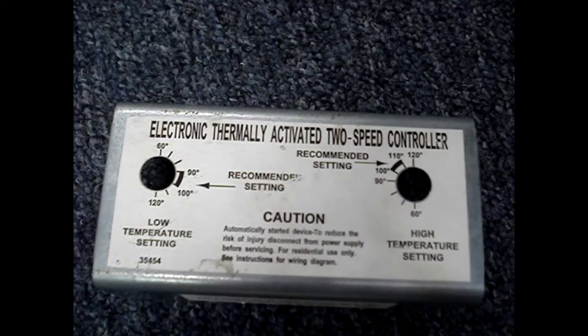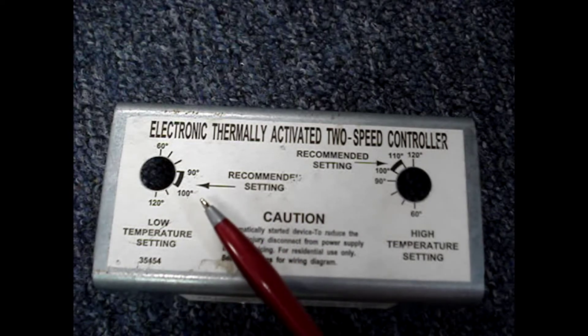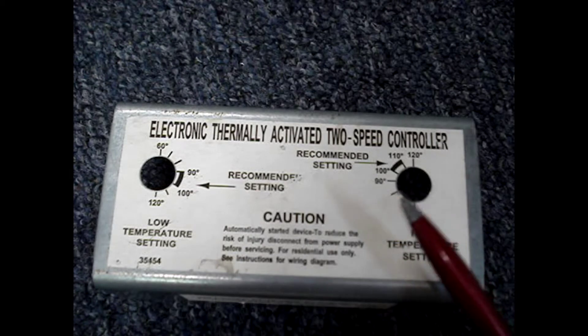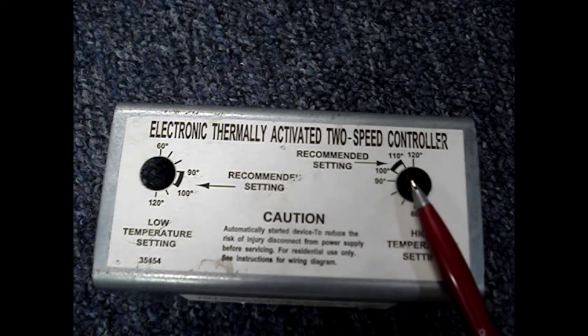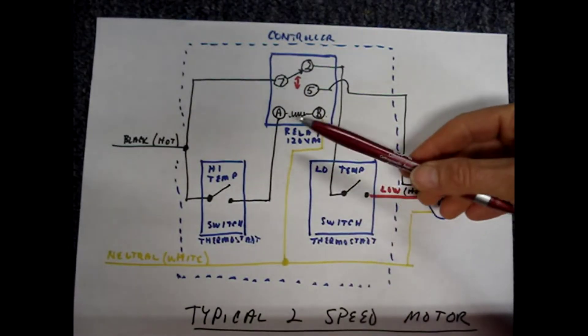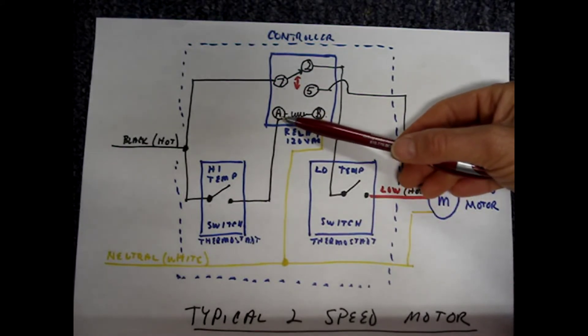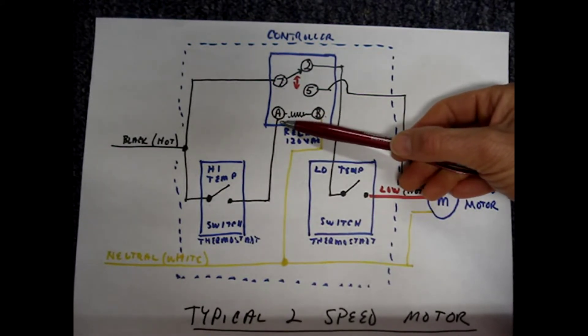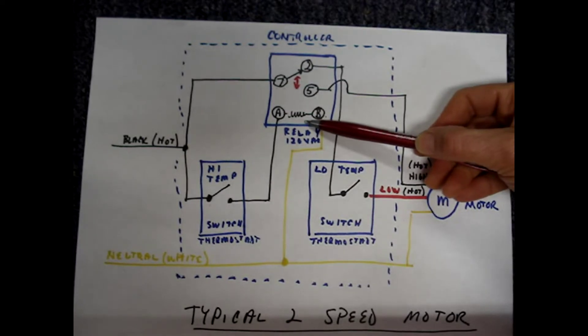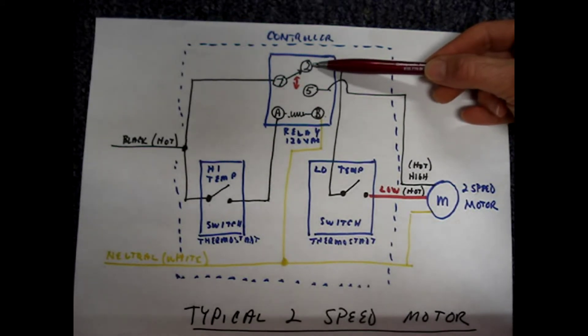Let's say that the fan is running on low speed because the attic temperature is between 90 and 100 degrees. And then the temperature increases to over 100 degrees. The high temperature switch closes and the hot is now present at terminal A on the coil of the relay. This energizes the relay and causes the contacts to change state.